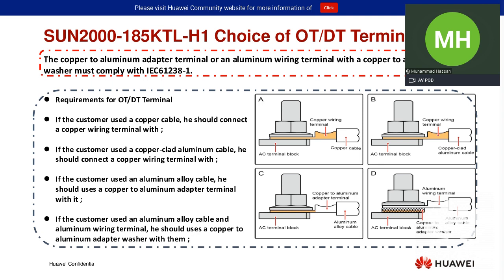Also, here is an important thing: if you are using aluminum cable, you must use the copper-to-aluminum washer inside the OT terminal, to protect against any kind of problems in the future.